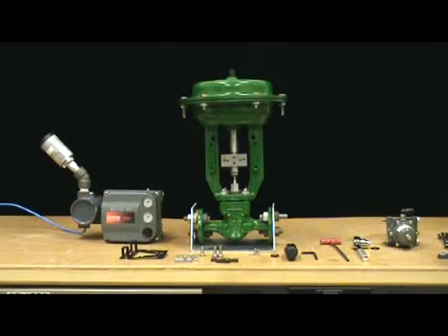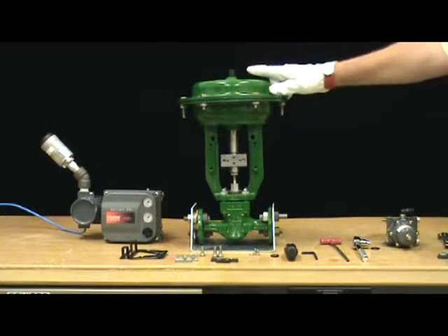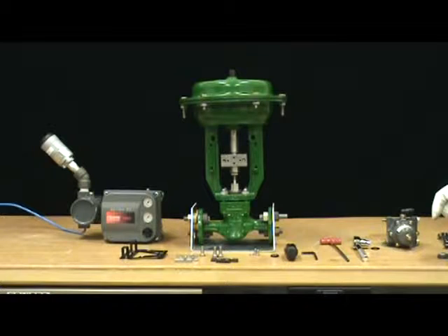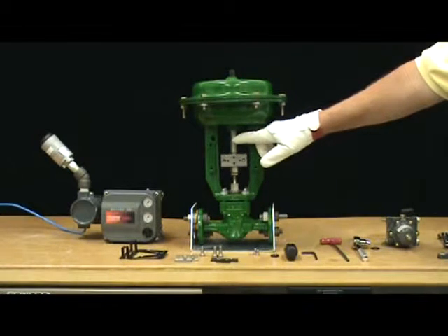We're going to be mounting a DVC 6200 on an air-to-open GX. Air-to-open can be identified by a vent in the top casing. We also have to identify the proper yoke side to mount the digital valve controller. Note the casing supply connection on the yoke leg.